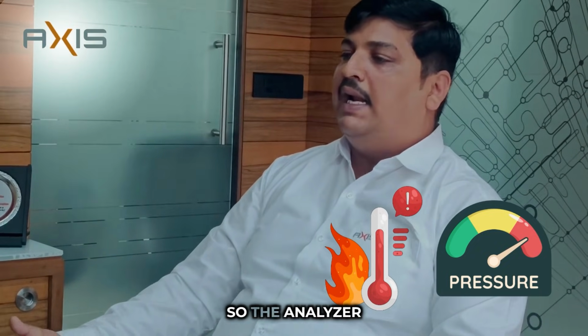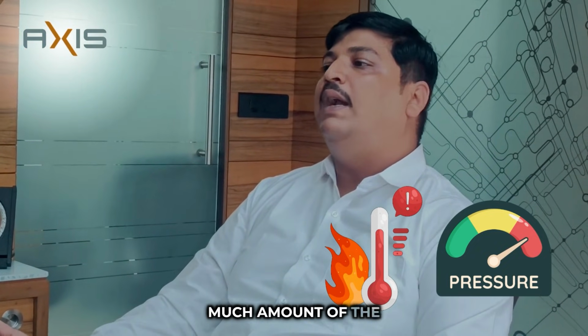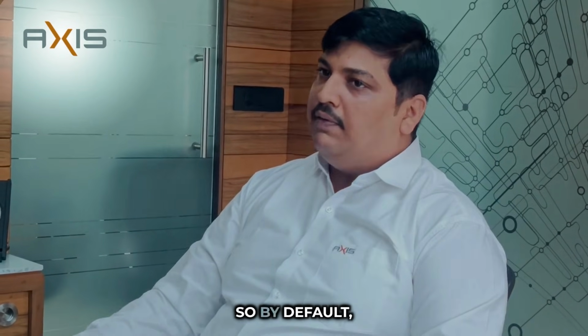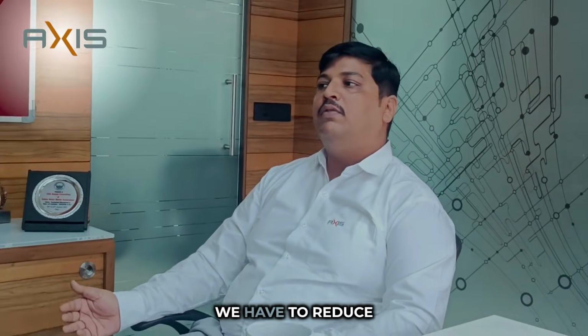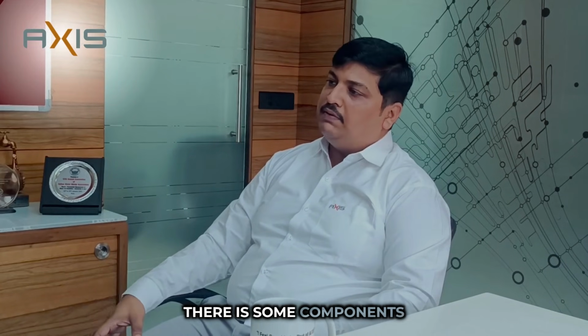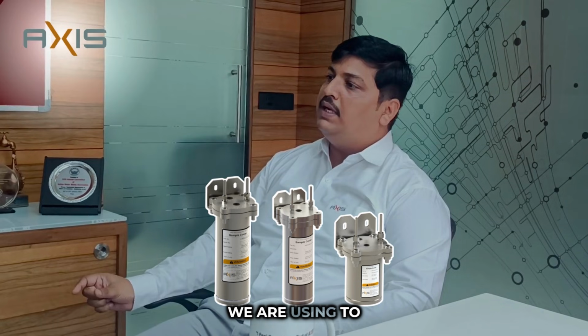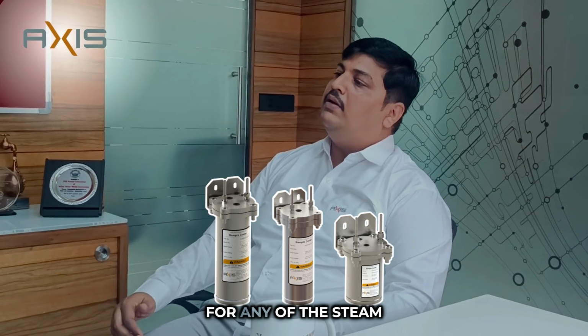Because what happens if we are talking about boilers? What is the boiler? There is high temperature, high pressure. The analyzer cannot withstand that much high temperature and high pressure. So by default we have to cool down the temperature and reduce the pressure. Exactly, the sampling system does the same thing for the SWAS. There are some components we use, like the sample cooler, to reduce the temperature of each of the steams of the SWAS.